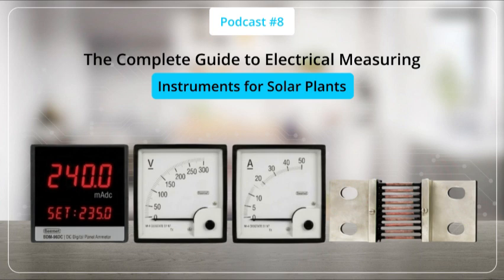more costly. As we come to the end of this discussion, it's worth understanding what happens when measurement goes wrong. Even small measurement errors can reduce a plant's efficiency in ways that aren't immediately obvious. Using the wrong tool for the job can damage equipment and create safety risks. Improper DC shunts or unstable power references reduce measurement accuracy and, in turn, energy output. Underestimating shading during planning leads to unexpected power loss once the system is running. Harmonic distortion that goes unmeasured can affect inverter performance and component sizing. Dirty panels that aren't being tracked through soiling measurements quietly reduce system efficiency over time. And incorrect voltage measurements combined with temperature fluctuations can result in the wrong repairs being made, which sometimes creates new problems instead of solving existing ones.